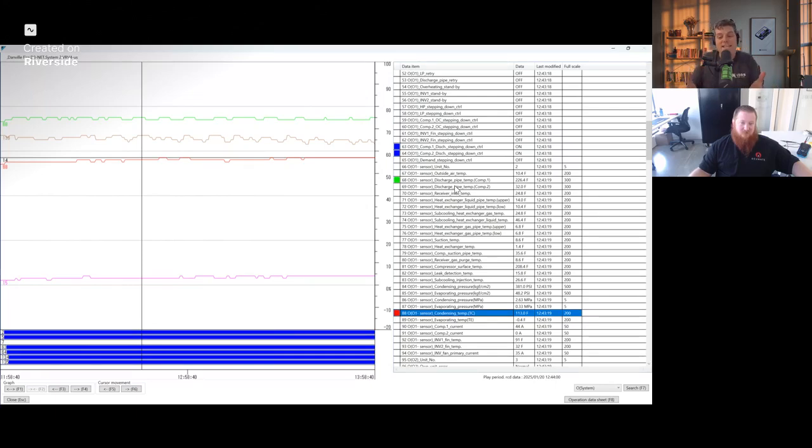And the reason is because it tells us so much about the compressor. It tells us so much about the refrigerant charge. It tells us about the system and its health and the oil and all of the things that go along with system longevity for VRV systems. So here you can see 226.4 over 113. We are over 100 degrees discharge superheat, which is a really bad thing, right? That means that we've got no oil in that compressor. We've probably got no refrigerant coming back to that compressor. This looks like a charge issue.